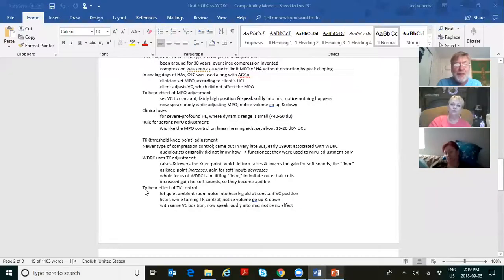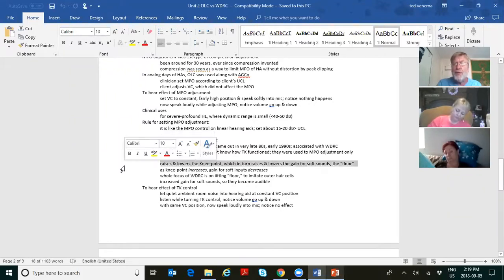Okay? So when you're talking, you're already at average inputs. The hearing aid is already in compression. Adjusting the TK, you can go and do that all night long. You're not going to hear anything because the TK adjusts the gain for soft inputs. Okay? So just kind of rounding off with common sense here, and then we can go home. All right. So WDRC uses the TK adjustment, which raised or lowered the knee point, which in turn raised or lowered the gain for soft sounds.